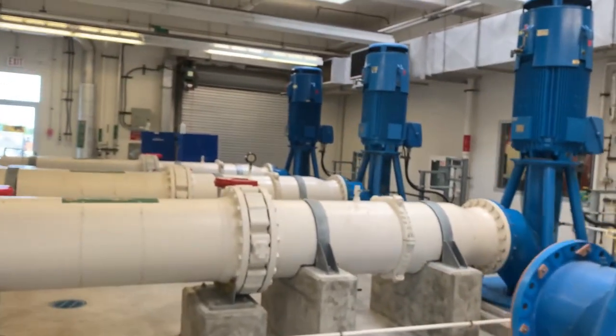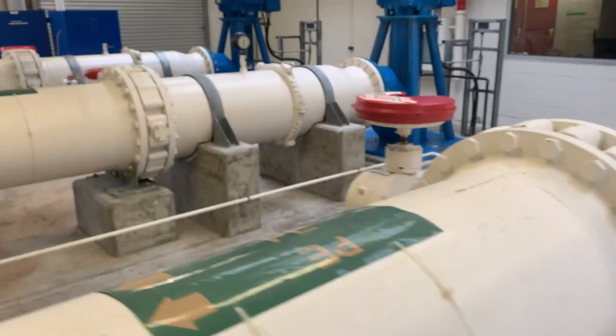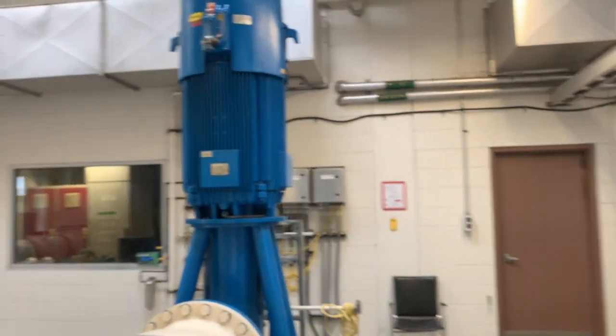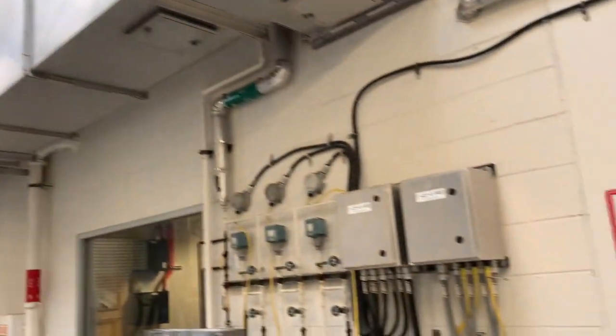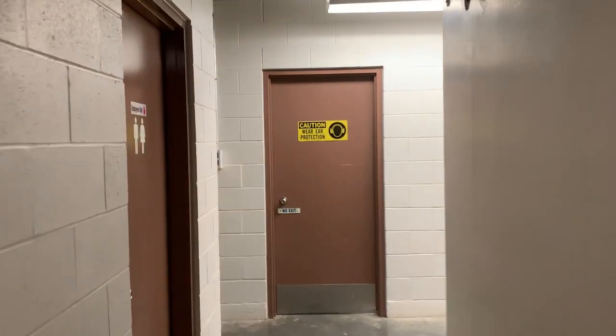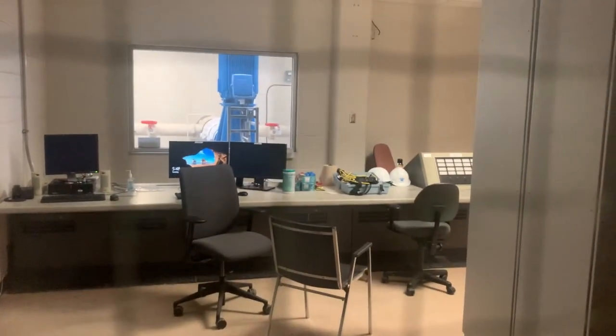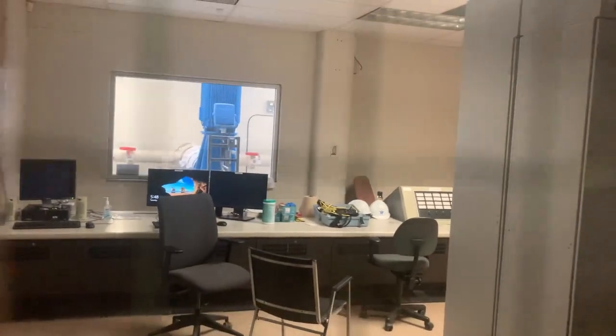Inside the trickle filter pump room, big pipes about two feet in diameter pump to three trickle filters — noisy, whining, with lots of electricity consumed. In the blower building we have another control room — no one's in there today, all locked up. In the blower room you need a lot of hearing protection. These are big centrifugal blowers: air comes in through a big shaft at the back through a muffler, into the blower where it's compressed in stages getting hotter and hotter, then out into a manifold through the wall and out to the bacteria.